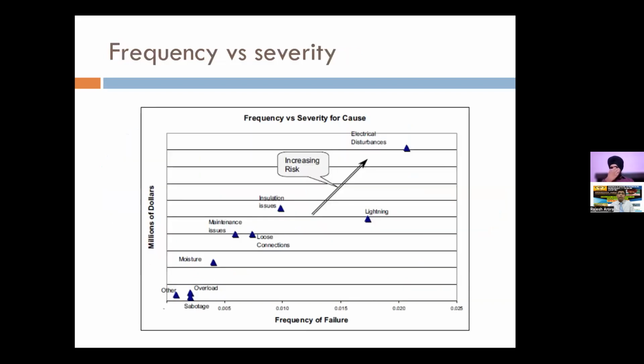So when we talk about frequency of failure versus severity, I have tried to plot what can be the frequency of failure. Electrical disturbances can occur many times, because when our system is connected and there are some operations, some lightning, some disturbances can occur. So these electrical disturbances are the most frequent, and these also cause the most damage to a transformer or a reactor. And when we comparatively see lightning issues, insulation issues, maintenance issues, these are less frequent and they cause relatively less damage to a transformer.